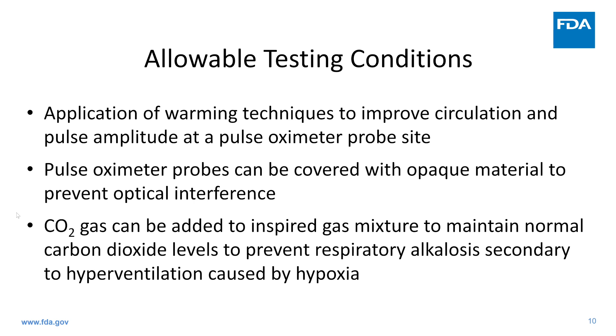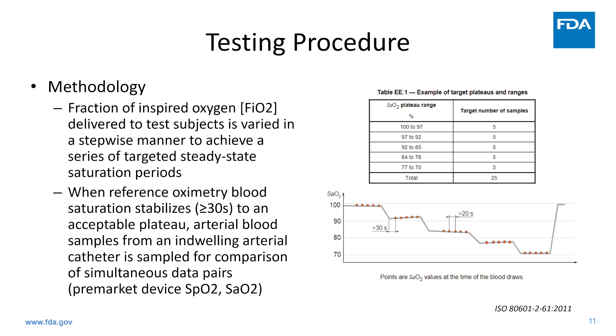A catheter is placed within the artery of all test subjects prior to desaturation during the studies and test procedures. A cleared pulse oximeter is placed as a reference to detect stable plateaus. The fraction of inspired oxygen varied in a stepwise manner to achieve a series of targeted steady state saturation periods. When the reference pulse oximeter stabilizes for 30 seconds or so, the arterial blood sample is taken and measured, and compared simultaneously to data pairs, so that basically you could measure SpO2 and SaO2 variance in real time.